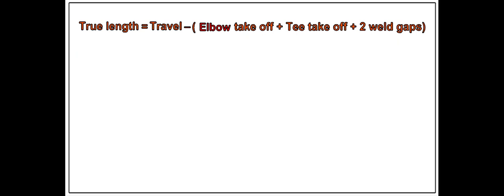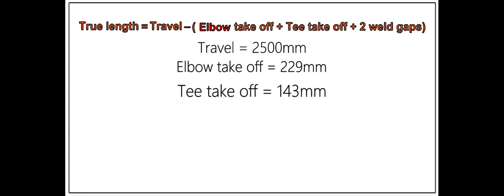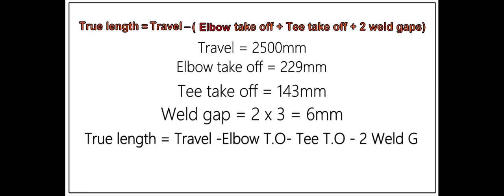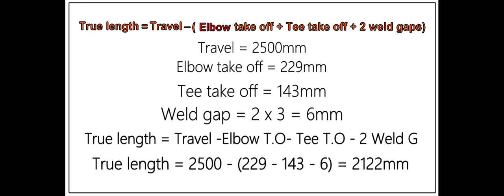We have all the required dimensions now. Deduct the takeoff of the tee and the elbow and two weld gaps from the travel length. The travel length is 2,500 millimeters. Elbow takeoff equals 229 millimeters. Tee takeoff equals 143 millimeters. Two weld gaps equals 6 millimeters. Let us apply the formula. The result is 2,122 millimeters.